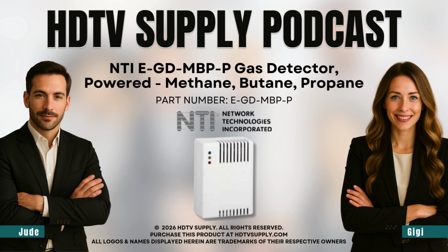I see. In some industrial environments, you might have low-level gas venting as just a normal byproduct of an operation. So you'd opt for level 2 to make sure the system only activates for a genuine leak, not just trace amounts in the air. That makes perfect sense. So that's the detection side.